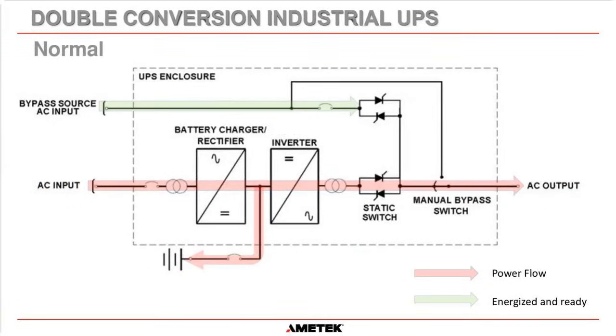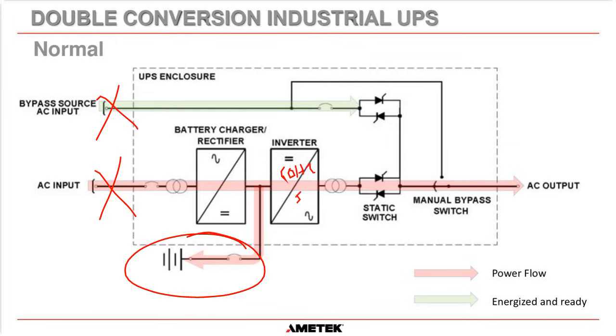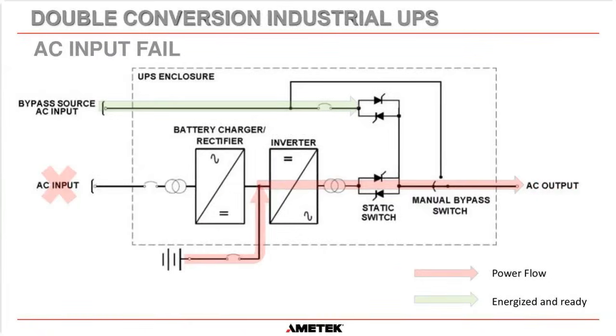It's this one here. So what Corey's asking is, if this fails and this fails, we go on to battery operation. The inverter has its own internal clock, as we call it in the industry, and it's set for 60 hertz for the US, 50 hertz for Europe and Asia, and it will run at its own frequency. It's 60 hertz. It will have no reference to the bypass supply, but you won't see any difference in the output. It's just as if we went on battery as normal. So if you lose AC input and bypass at the same time, you'll go onto battery, and your loads will still be protected. So it's a good question.